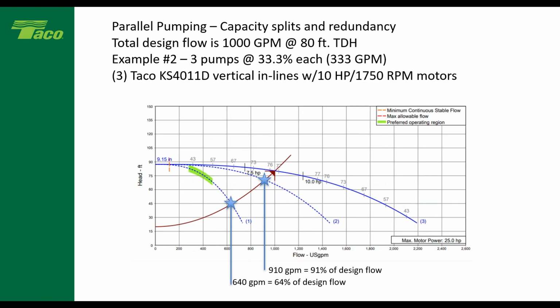However, if I look at that same setup, I can drop my motor horsepower down to 10 horsepower. Okay, now what I'm going to get is, are you ready for this? In this scenario with three pumps in parallel, so three pumps are handling the entire load, if one pump of that three fails, I can deliver 910 GPM or 91% of the design flow.